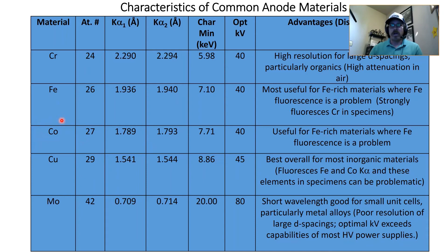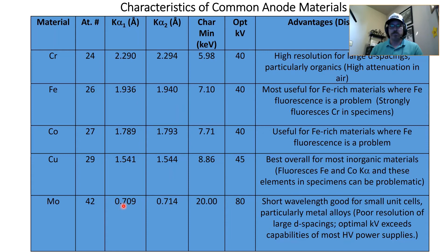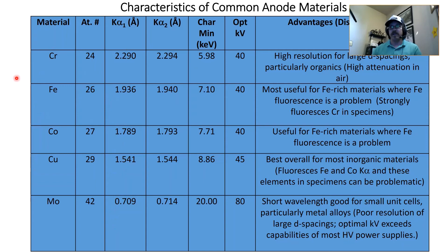Copper is the workhorse target, but it fluoresces iron and cobalt, so it's not ideal for those materials — though we use it anyway at UTEP. Molybdenum has a short wavelength of 0.7 angstroms — roughly half of copper's — making it good for small unit cells. The smaller the wavelength, the smaller the D-spacing you can resolve. Different target materials offer different pros, cons, and wavelengths for the diffractometer.